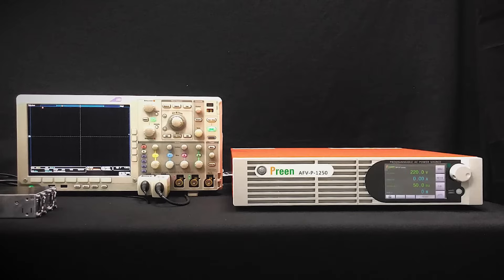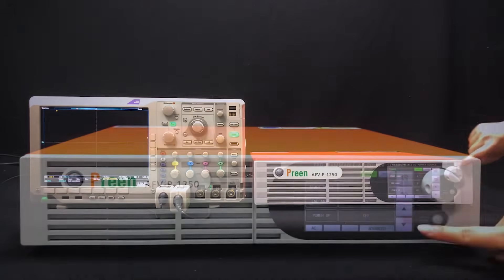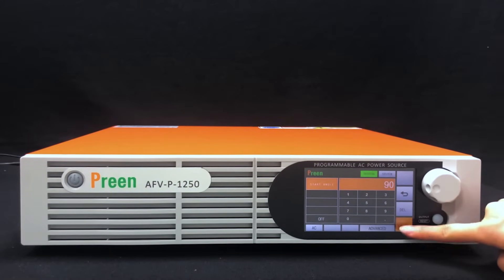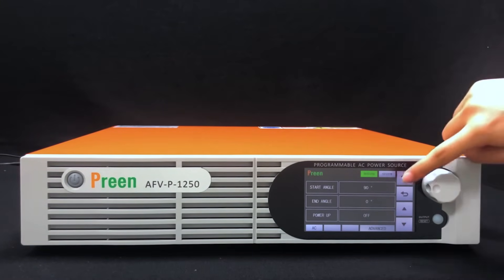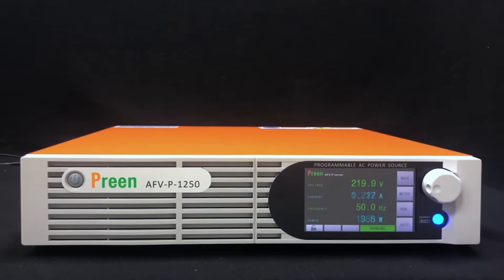Today we use the Preen AFV-P-1250 model with an oscilloscope and switching power supply for a demonstration. If the turn-on angle of input voltage is 90 or 270 degrees, the inrush current will start at its peak value. The user can set the start and end angle with the AFV-P series to simulate the maximum peak current at the initial power-on stage, ensuring product reliability at different input conditions.